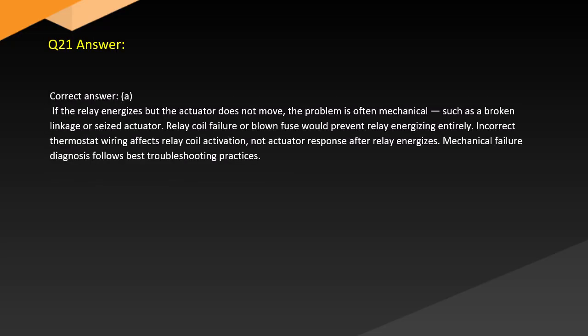Answer. Correct answer. A. If the relay energizes but the actuator does not move, the problem is often mechanical, such as broken linkage or seized actuator. Relay coil failure or blown fuse would prevent relay energizing entirely. Incorrect thermostat wiring affects relay coil activation, not actuator response after relay energizes. Mechanical failure diagnosis follows best troubleshooting practices.